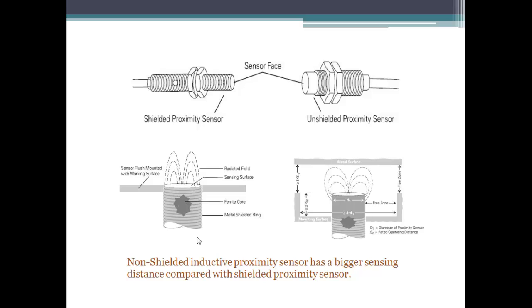In contrast, non-shielded inductive proximity sensors have an exposed coil. For this reason, the non-shielded model can induce a larger electromagnetic pattern and has a bigger rated sensing range compared to the shielded inductive proximity sensor.